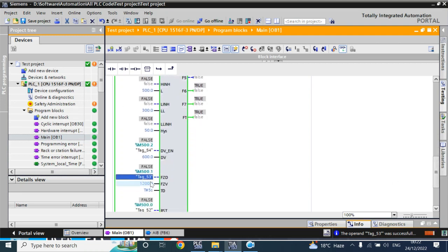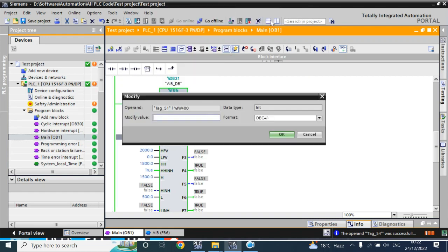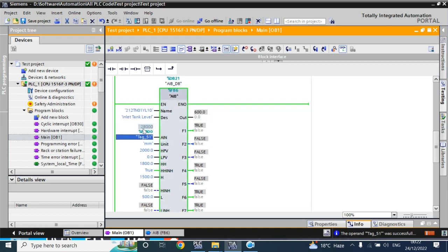The freeze instruction works as expected. Now for the default value: if the default value enable pin is enabled, the output will copy from the default value when a hardware failure, underflow, or overflow occurs. For example, entering 28000 causes an overflow because the nominal input range is 0 to 27648 — entering 28000 exceeds this range, so it is over-range and the output takes the default value.